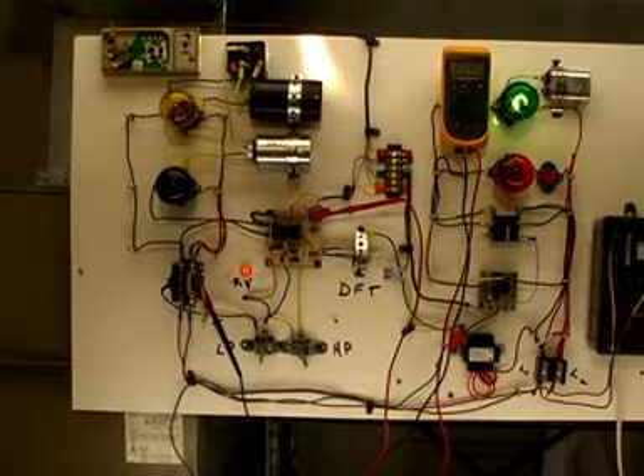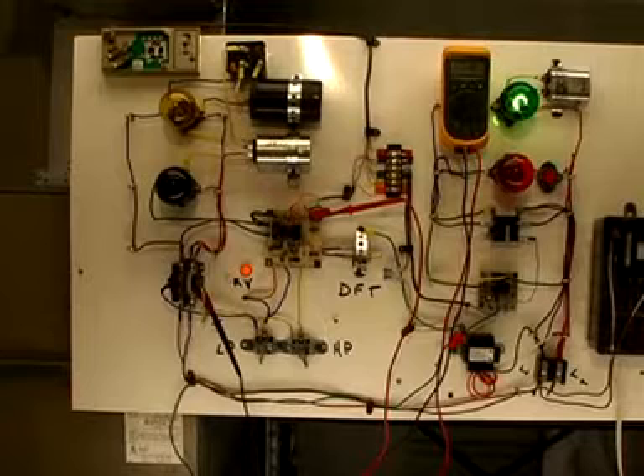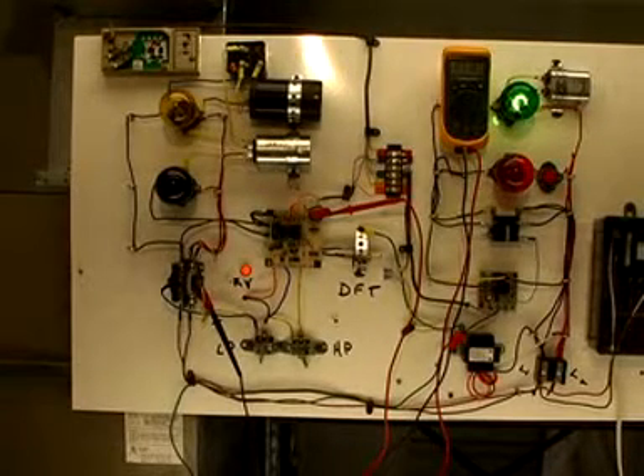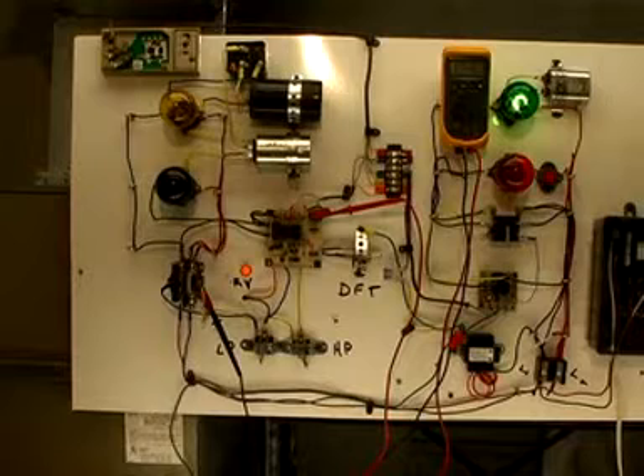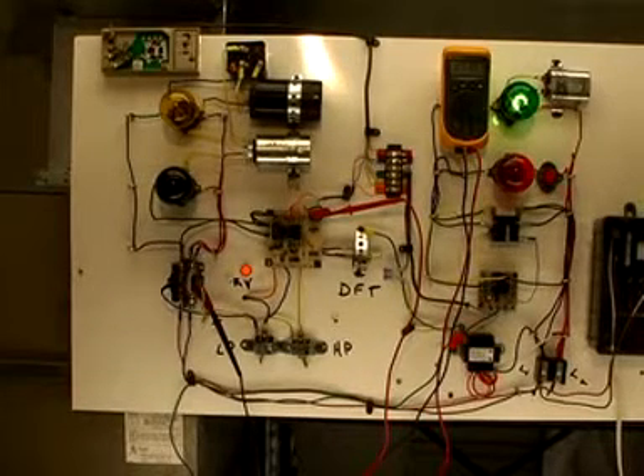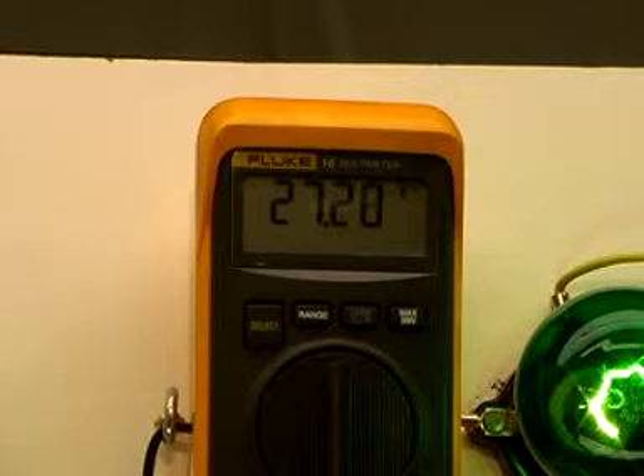The blower's running, the condensing unit's not running, and the reversing valve is energized. So we've already got a meter probe down here at the front side, or the hot side, of the contactor, and we'll see that the voltage is 27 this time, so this is a little bit different than it had before. Now, some folks might think at this point, well, obviously the contactor's messed up, but don't be too hasty.